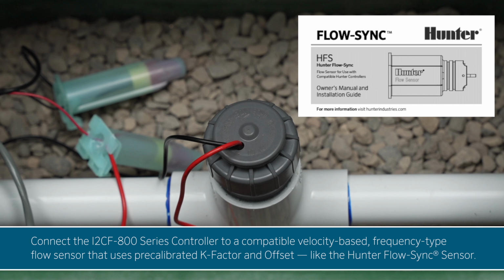To monitor system flow, connect the I2CF 800 series controller to a compatible velocity-based frequency-type flow sensor that uses a pre-calibrated K-factor and offset, like the Hunter Flow Sync sensor.